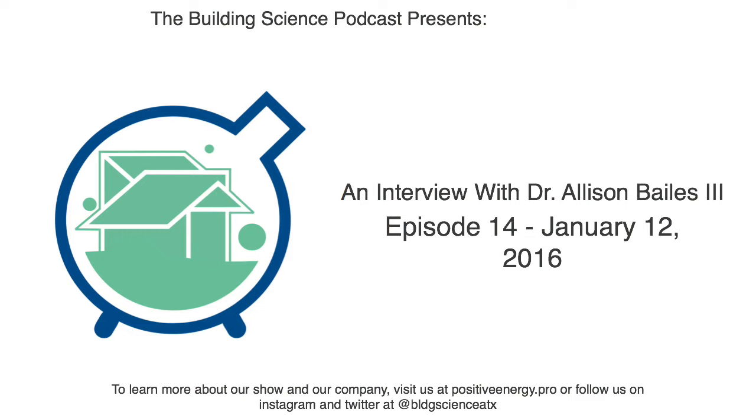So let me just make some numbers on it. I'm going to say that our example house for this podcast is 2,500 square feet, and it's a 3-bedroom. So then we'd have 25 CFM based on the square footage. Yep. And then 3 bedrooms, so we do 4 people, 7.5 each. That's 30. So that's 55 CFM total. Yep. And that's based on the 2010 standard. Yes. Okay. And that's continuous. 55 cubic feet per minute, CFM, continuous air 24 hours a day, 7 days a week.